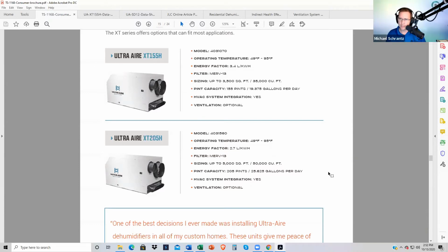For my own understanding, as a friendly reminder to the audience: dedicated ductwork means multi-point ductwork penetrating into the house at common areas, say the master bedroom, living room, the office—not every room. The reason you'd separate that out from your primary air conditioning system, which may have a whole-house dehumidifier on it, is because that ERV in a humid setting may be able to better complement your goals of 50% relative humidity or less, with more fresh air coming in and not having any secondary concerns compared to just having a venting dehumidifier. Is that accurate, or did I butcher it?